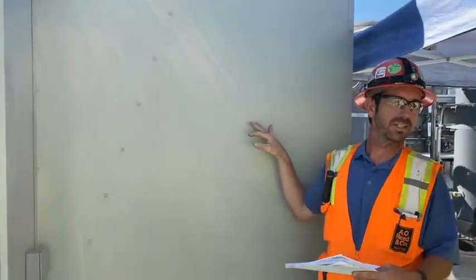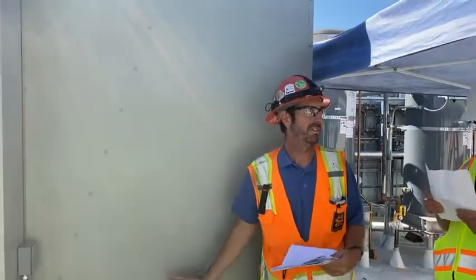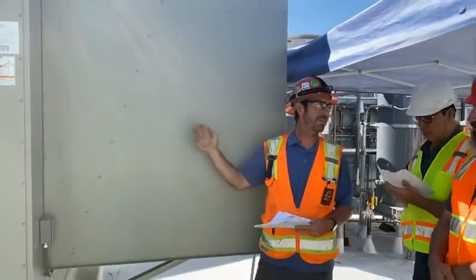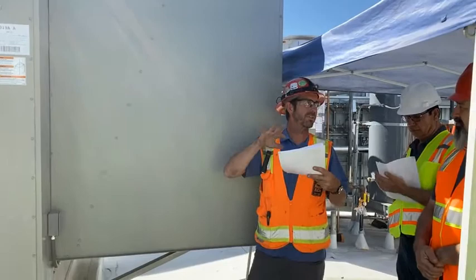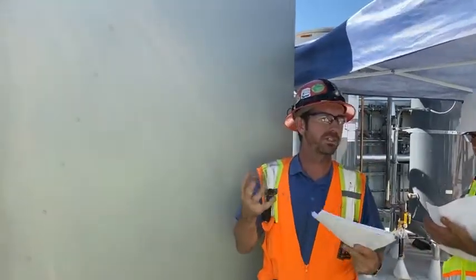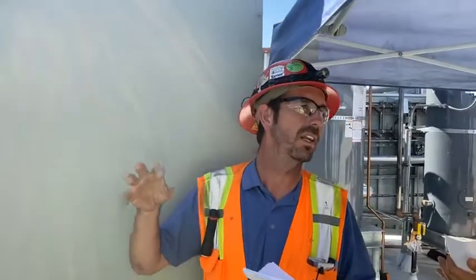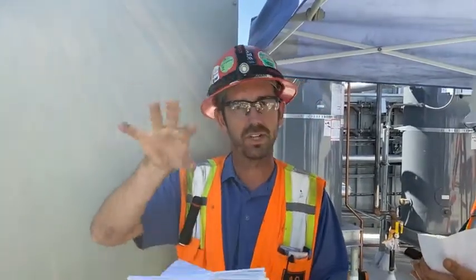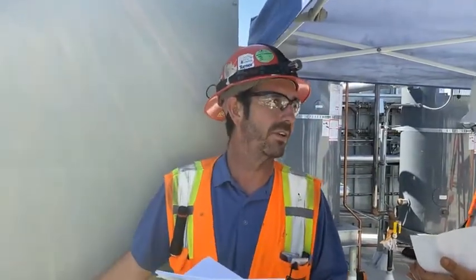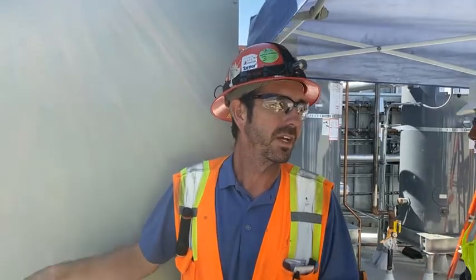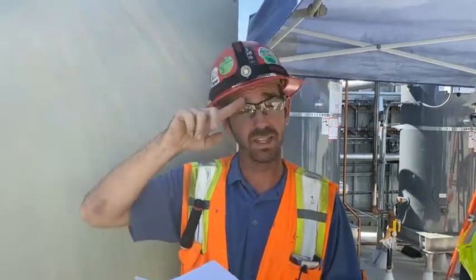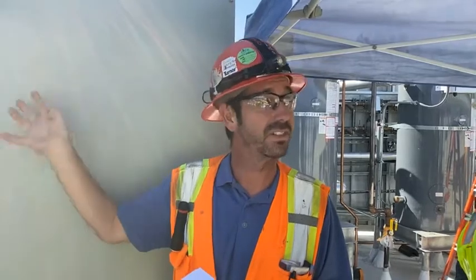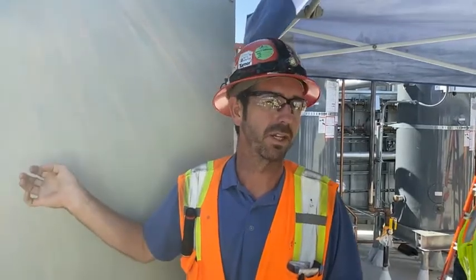Starting on this end right here, this big plenum box is going to be your outside air intake. Up inside, we have moisture eliminator filters, okay? It's an aluminum screen, little crisscrosses with a little bit of mesh. So any bit of moisture that's in the air is going to hit that screen. It's going to attach itself to the screen and drip down on the ground outside the unit on the roof, so we don't saturate filters on the inside of the unit, so we don't get moisture inside the unit, okay? You're going to want to clean those.